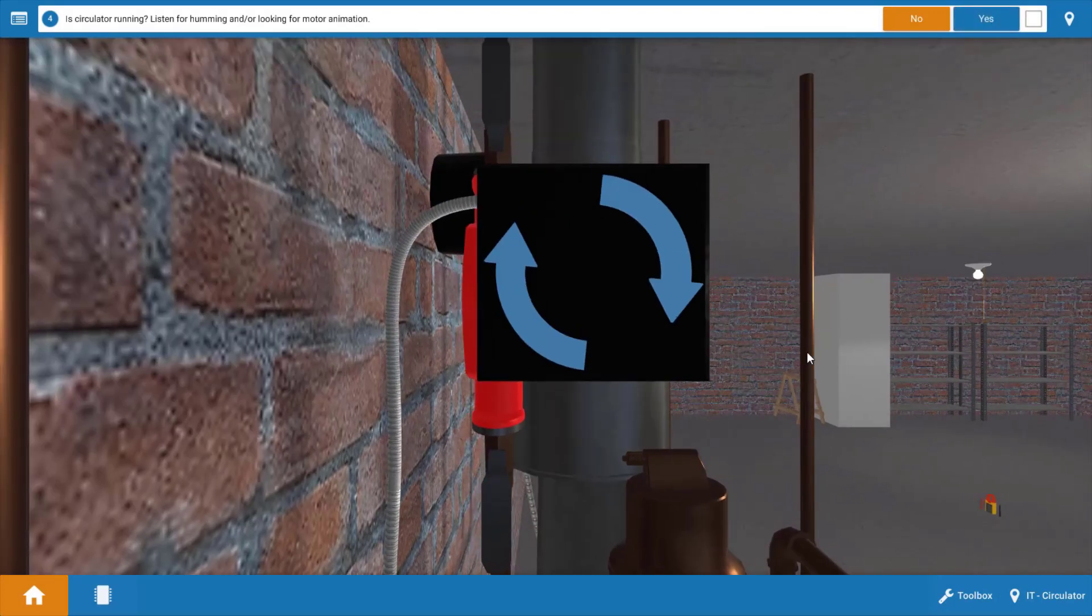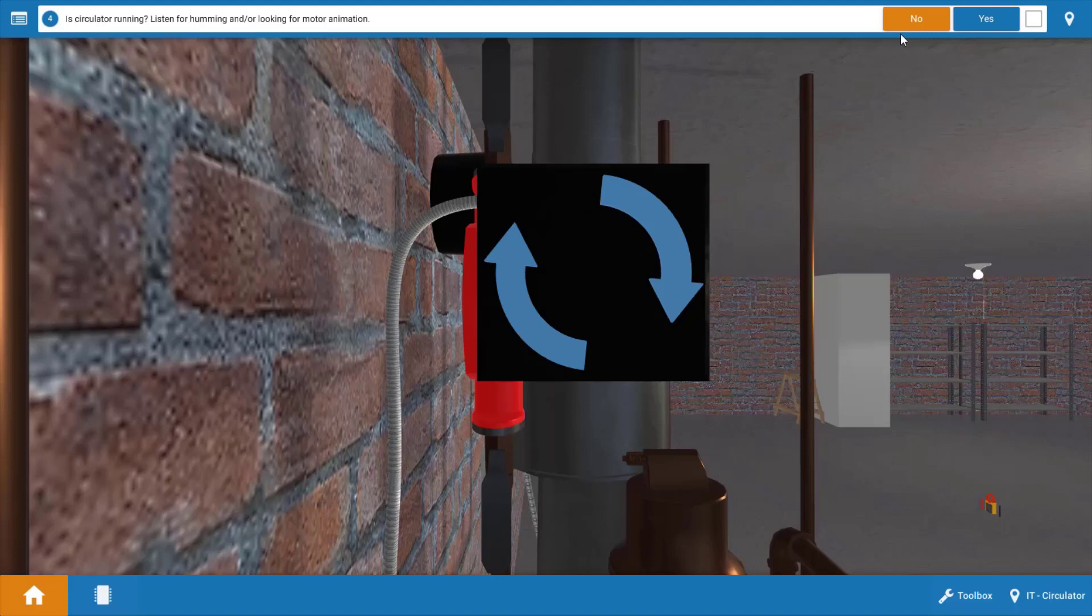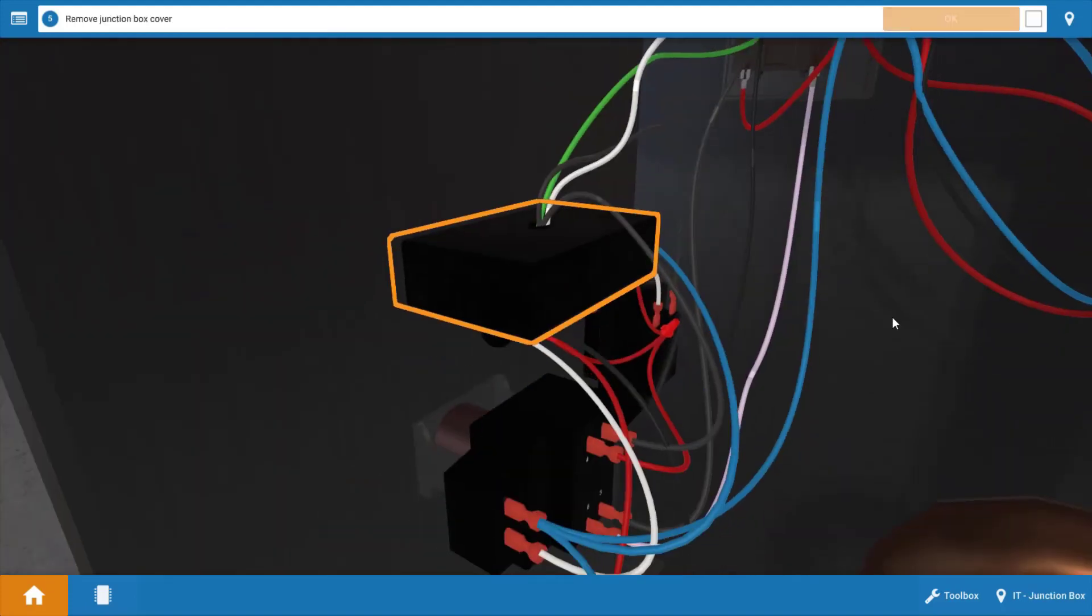Next we go to our circulator pump and we can see that the circulator is also not operating. If the circulator was running these blue arrows would be spinning. So neither one of our primary electrical loads is operational.